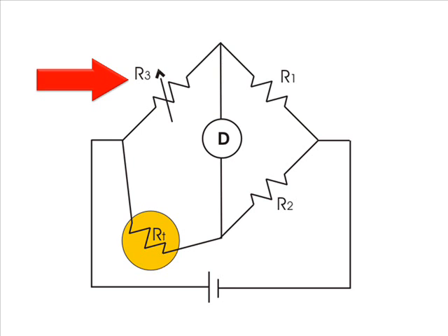The balance of the bridge is achieved at different positions of sliding contact of variable resistor. If the positions of sliding contact of the variable resistor are calibrated in temperature scale, we can directly measure the temperature of the place where the RTD bulb is placed.